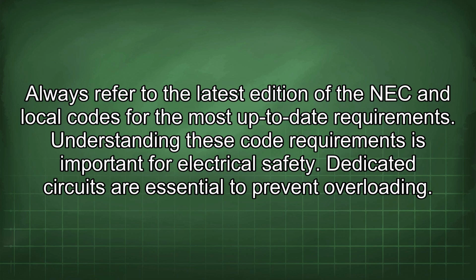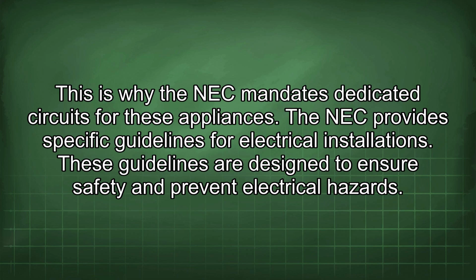Dedicated circuits are essential to prevent overloading. Overloaded circuits can lead to overheating of wires, which in turn can cause fires. A 15-amp circuit, for example, is designed to handle a maximum load of 15 amps continuously. When appliances like dishwashers and disposals, which have high current demands, share a single 15-amp circuit, the circuit can easily become overloaded. This is why the NEC mandates dedicated circuits for these appliances.